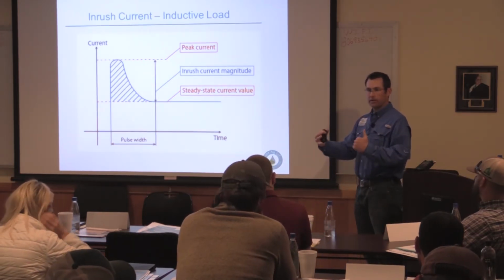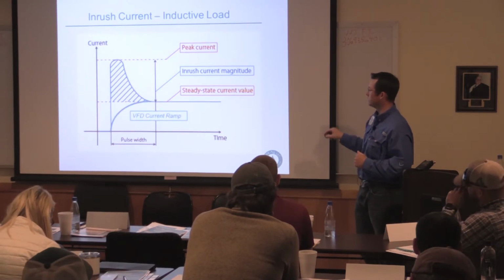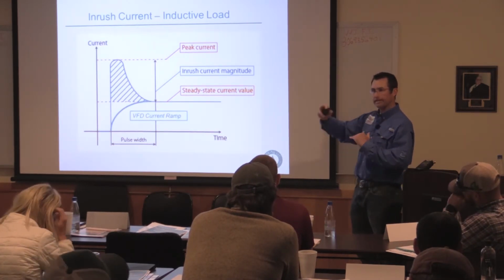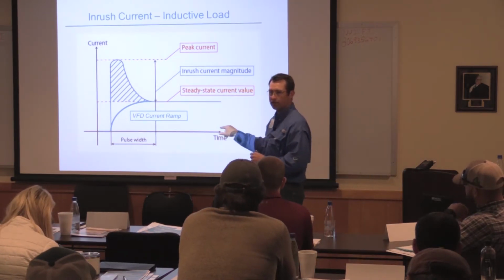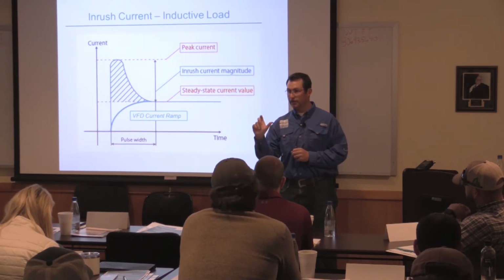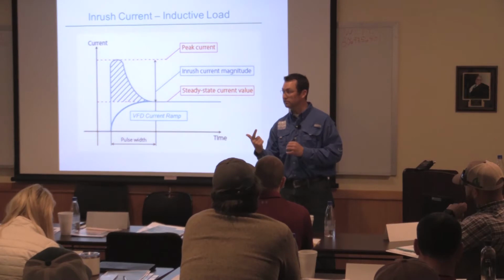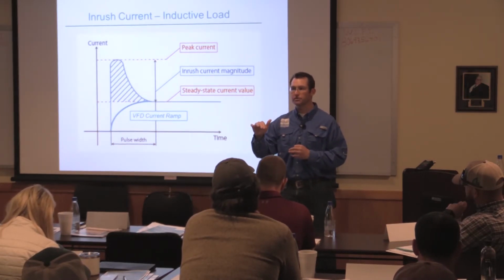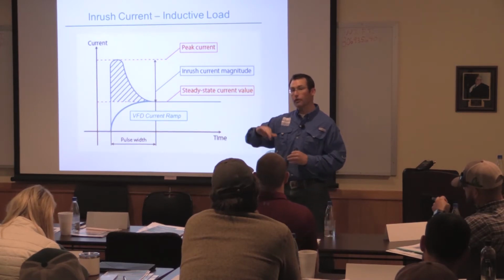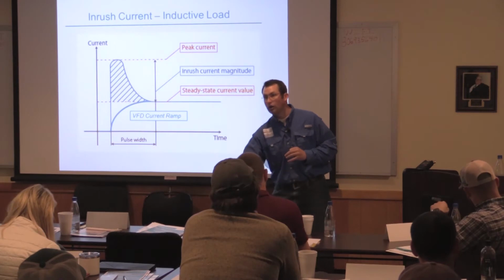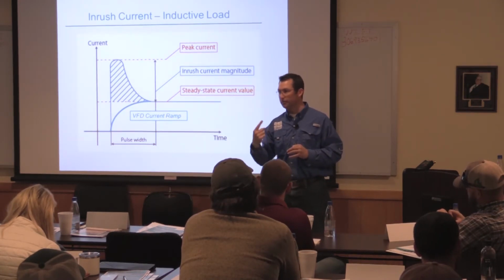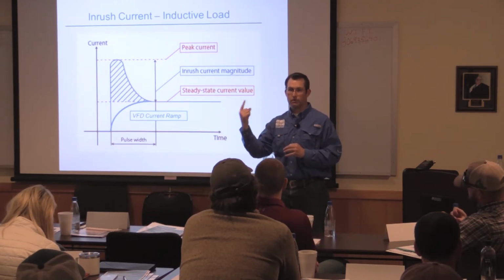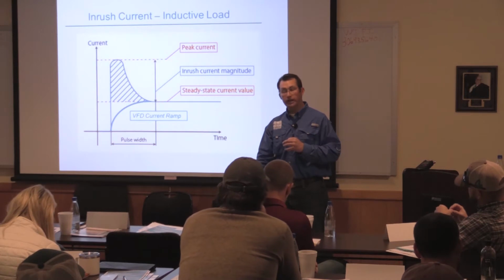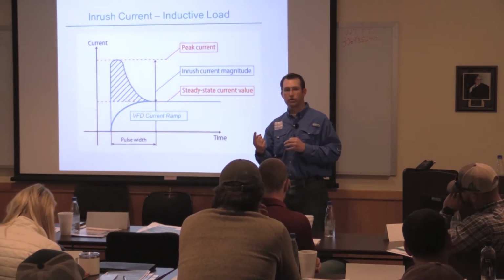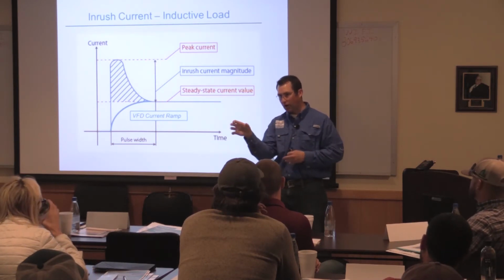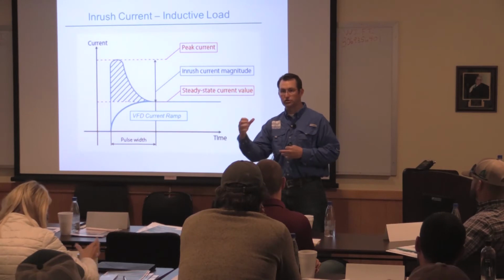When you're generating your own power and you've got a limited source, you want to avoid that, and this is what a VFD allows you to do. You'll be able to ramp it up where you never really exceed that level. There are tricks you can do with a VFD because you're dealing with frequencies where you can give it basically a signature of full voltage but lower amps, so you can spin it really fast to start it without loading it. Think about a well pump: you don't need all the horsepower of that motor until you've lifted the water from the bottom all the way to the top of the column. So you can start spinning that pump pretty slowly to ramp up without much grief. You might think the water's way down there and it needs all the power at the start, but it doesn't — it just needs enough to spin it. If you go out to your vertical hollow shaft, you can probably take the cover off your motor and spin the nut by hand. That's how much power it needs to start, until it gets a water column.